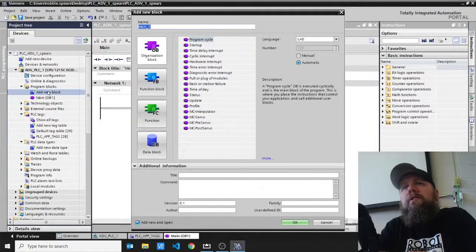So if we have a super long program, it might take a super long time for it to do its thing. If we have something that is dependent upon like real world timing, like we need something to happen every second, regardless of how long, we could have something like a cyclical interrupt, and that function would operate outside of main and would keep going and trigger the things that are in it every second. Okay.